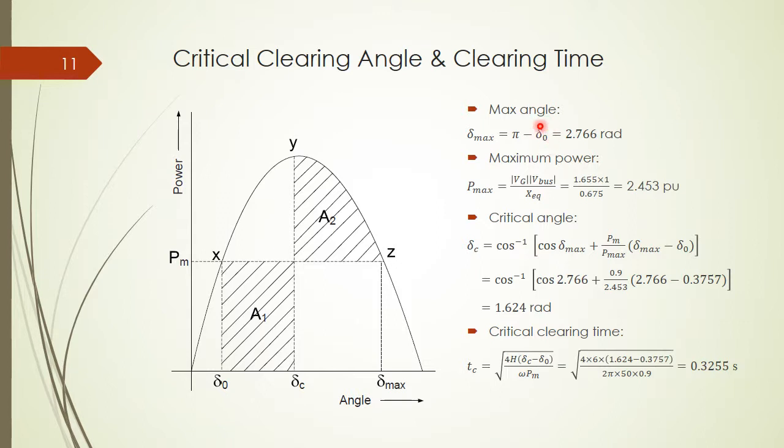After finding the initial condition delta_0, we can find out delta_max, which is pi minus delta_0. And then the maximum power will be given as P_max equals V_g amplitude times V_bus amplitude over X_equivalent, which is here. The critical clearing angle delta_c will be given by comparing the area A1 and A2 here. We have the formula to do that. The formula says that it is cosine inverse of (cosine delta_max plus P_m over P_max times (delta_max minus delta_0)). Replacing the numbers here, we have 1.624 radians.